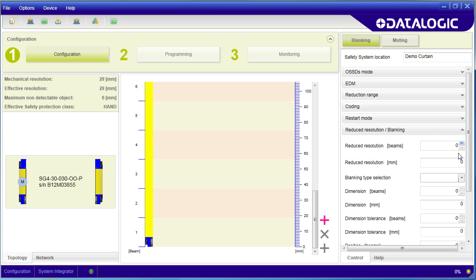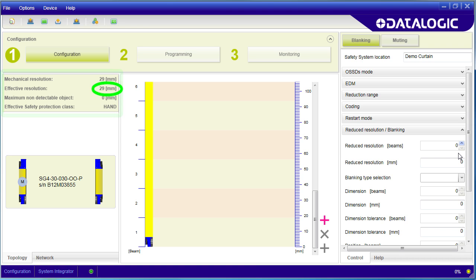Right now we are using all of the beams and have full coverage. This box up here tells us that for this light curtain we can detect any object that blocks more than 29mm of the light beams, which makes sense because if you look at this chart you see the light beams are spaced a little less than 20mm apart.